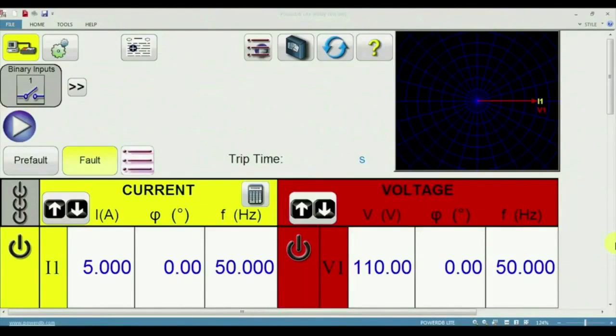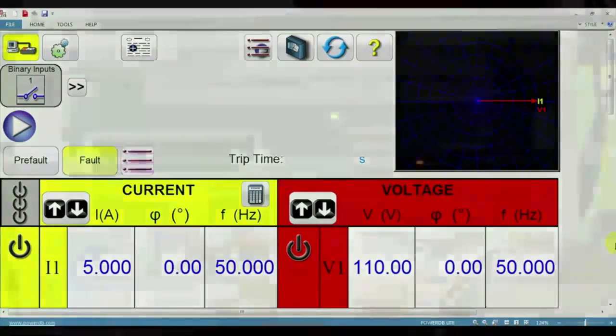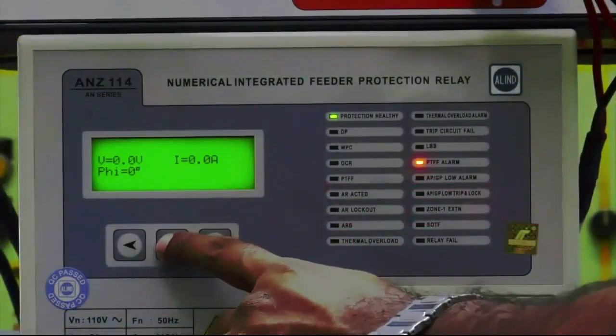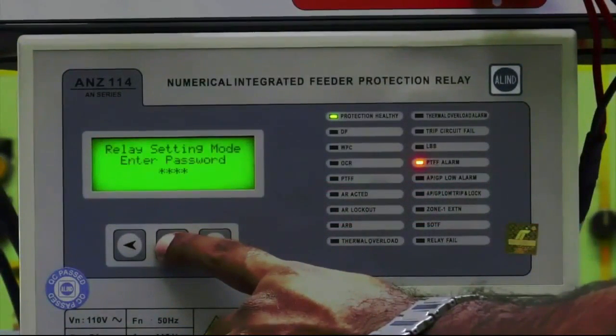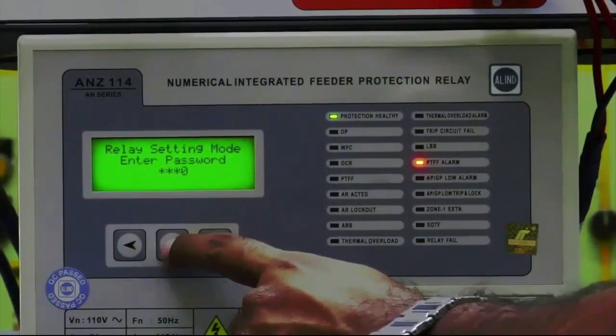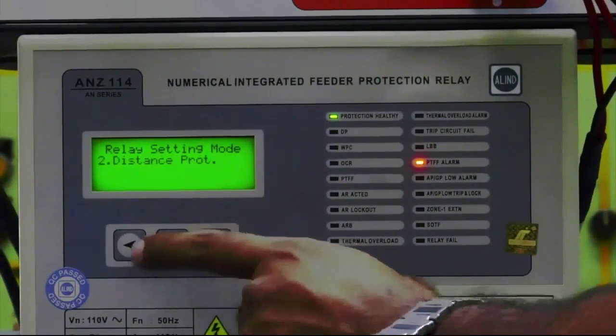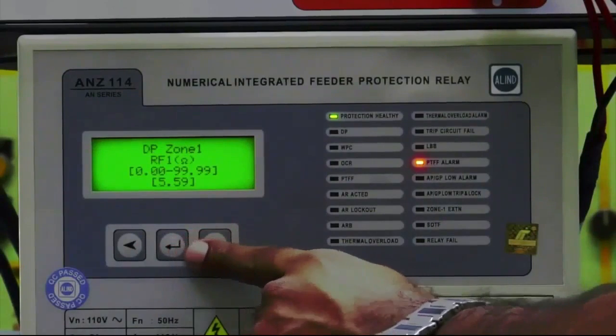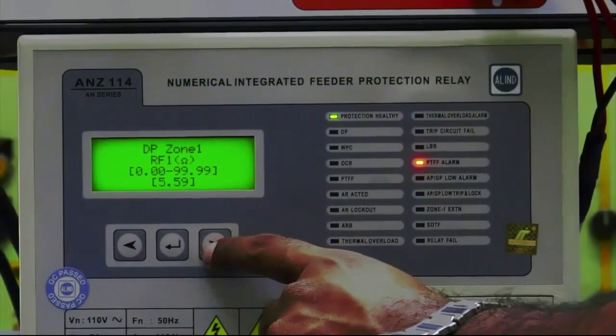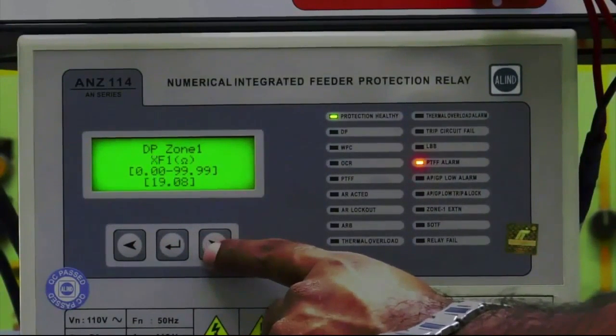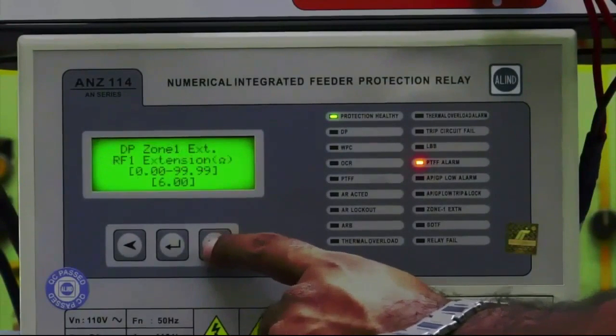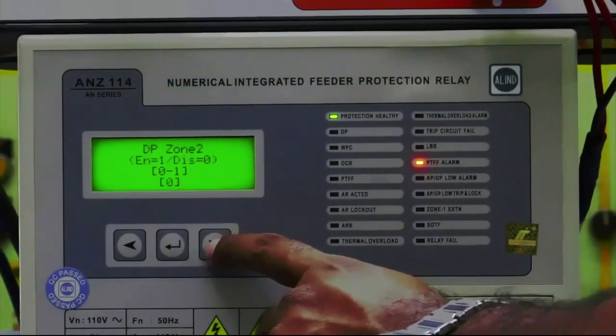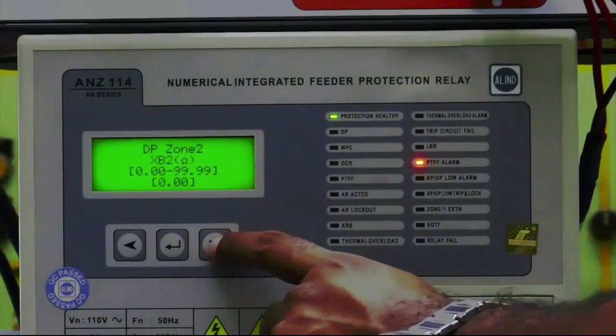In this video, we are going to see how to test the distance protection function. So before starting the test, we have to check the settings. So navigate to distance protection. So you can see I'm able to see values like RF1 5.59, XF1 19.08, RB1 5.59, XB1 4.77. We are not using zone 1 extension, zone 2 and zone 3 in this example.